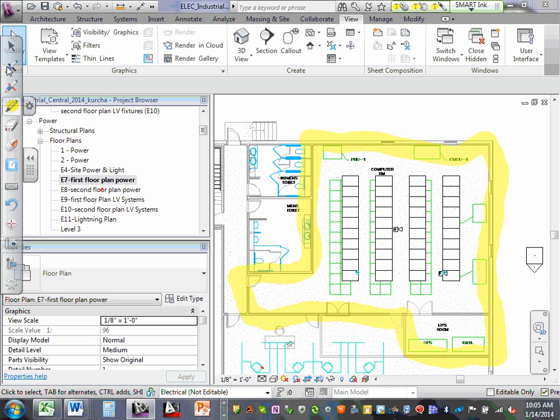Because even though the airflow is even greater in the subfloor than it is in the room itself, and that's simply a factor of volume, right? There's far less volume in the subfloor, which is the same square footage, but it's only, let's say, 12 inches deep or 18 inches deep. Whereas the room is 9 foot by the same square footage. What we have done in the past is we did half the ceiling placement of the smoke detectors.